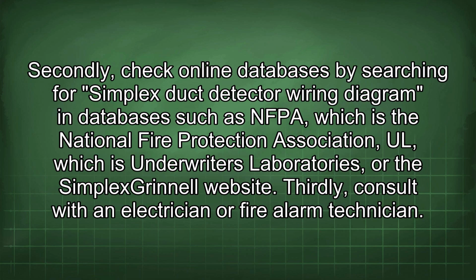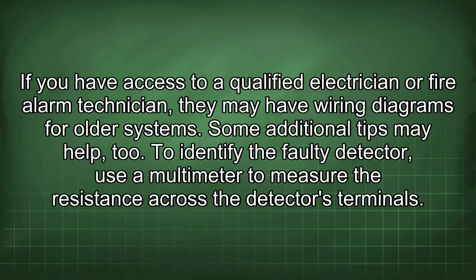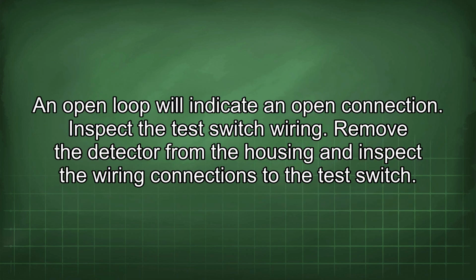Thirdly, consult with an electrician or fire alarm technician. If you have access to a qualified electrician or fire alarm technician, they may have wiring diagrams for older systems. Some additional tips may help too. To identify the faulty detector, use a multimeter to measure the resistance across the detector's terminals. An open loop will indicate an open connection.